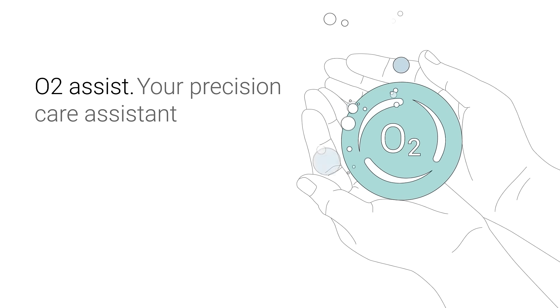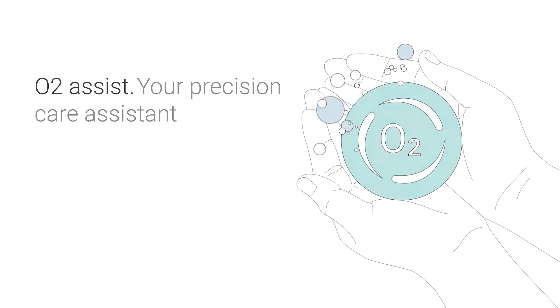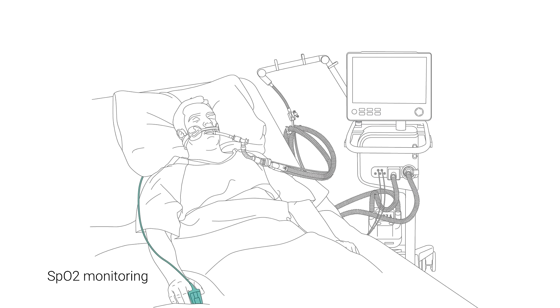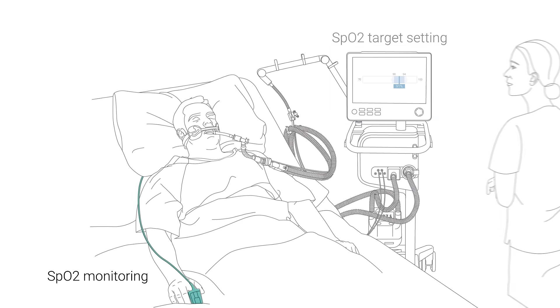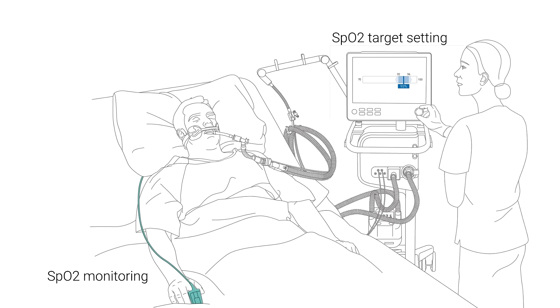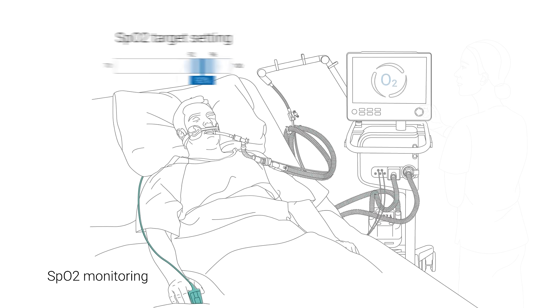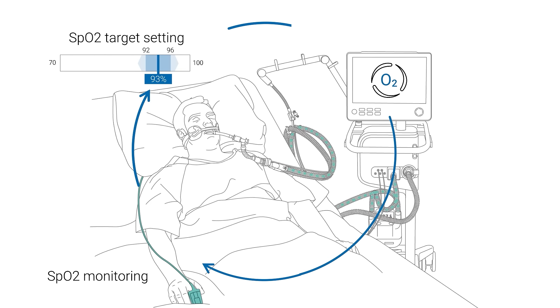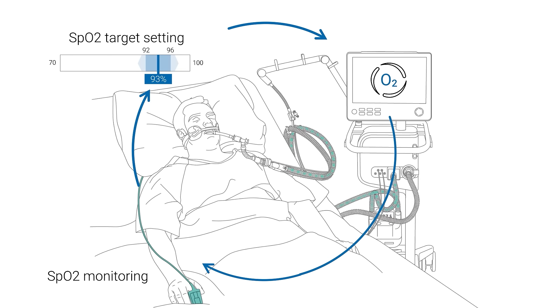What does O2 Assist do? O2 Assist continuously monitors patient SPO2 values, compares them with the SPO2 target range you have set for your patient, and adjusts oxygen delivery constantly to meet your patient's real-time needs.